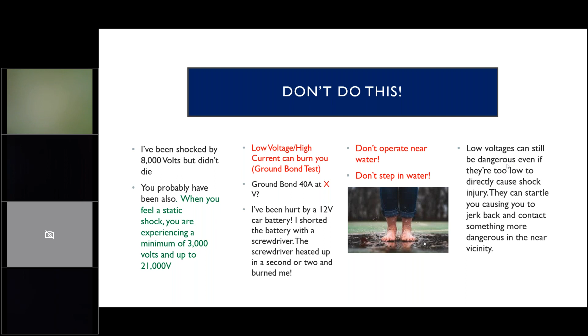So are HIPOTs safe? Our HIPOTs, and here's a model, a 95X, typical maximum output is 50 milliamps. So you can see that's below the threshold of 100 to 200 that's typically lethal. On the V7X, in AC, 20 milliamps max, 10 milliamps DC. Now, you can also put current limits on the HIPOTs so that they don't even get to 50 milliamps. So, for instance, you can establish a failure if it hits 30 milliamps and then say stop on failure. And you can also buy a 95X and say, I don't want 30 milliamps, so we'll limit the current so you don't get that.